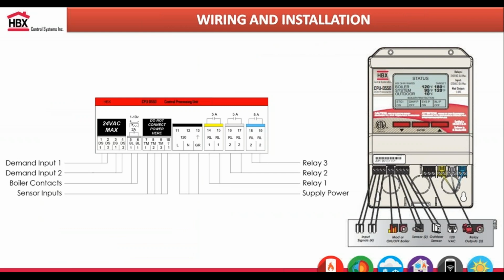Again, in terms of wiring, it's pretty straightforward. There are 2 demand inputs for your heating device. If you want to control domestic hot water, you can use the demand input, and then you just use the last 4 relays to control as many boilers as you want on the controller. So you can do a maximum of 3 boilers, and we have a maximum of 4 contacts. So if you were utilizing 3 boilers, you can control 1 pump.